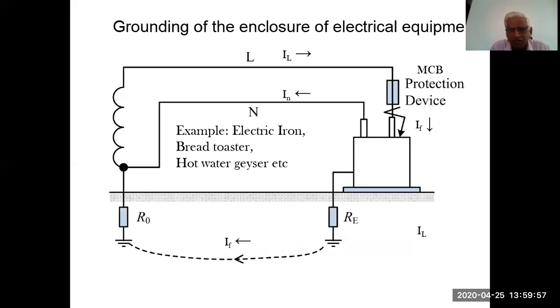The electrical item, like an electrical iron, is also earthed through its third pin. That is called the earth pin, whose diameter is more and whose length is more. So when you insert it, first the earth connection gets connected, and then the phase and the neutral come into the picture. There is a current flowing through the line and through the neutral, going back to the supply system, making a circuit. But accidentally the phase wire has fallen on the body, and the body is also earthed here. So the fault current goes through the body to the earth and back to the neutral. Thus the circuit is closed.